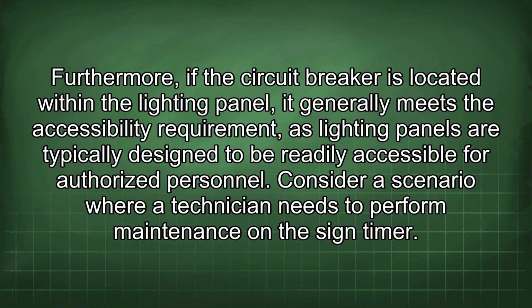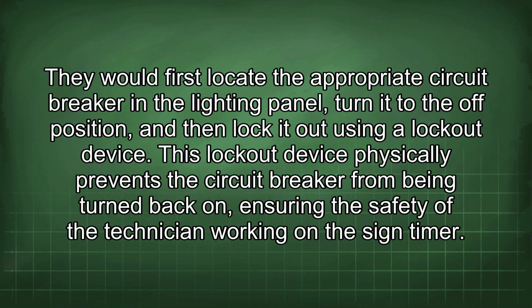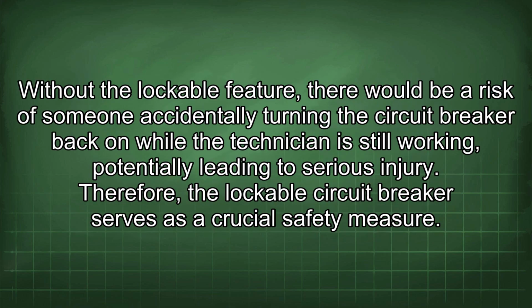Consider a scenario where a technician needs to perform maintenance on the sign timer. They would first locate the appropriate circuit breaker in the lighting panel, turn it to the off position, and then lock it out using a lockout device. This lockout device physically prevents the circuit breaker from being turned back on, ensuring the safety of the technician working on the sign timer. Without the lockable feature, there would be a risk of someone accidentally turning the circuit breaker back on while the technician is still working, potentially leading to serious injury. Therefore, the lockable circuit breaker serves as a crucial safety measure.